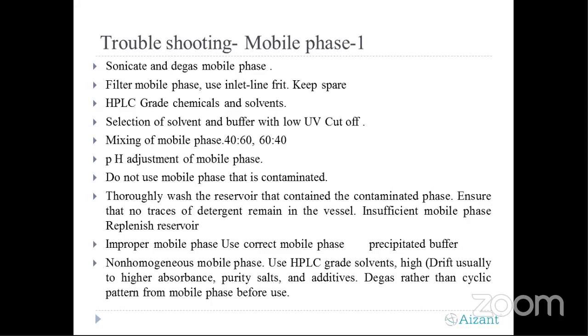Your pump pressure will be lost. There will be air entrapment in the tubings and more. You have to clean the inlet filters of the mobile phase tubings. What you can do best is sonicate them in methanol or water before attaching them to the tubing, and then attach them to the inlet. You have to use HPLC grade chemicals and solvents.